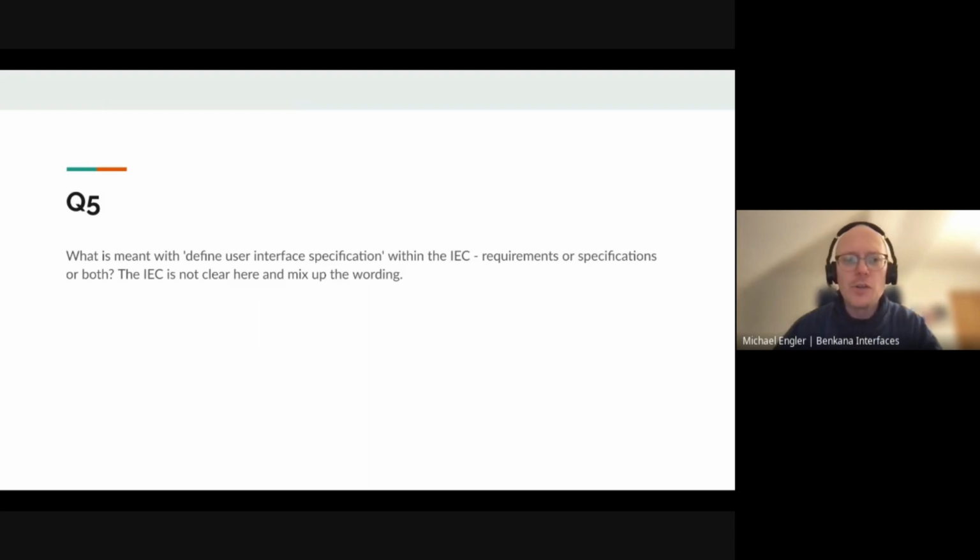So screenshots is not a good idea. What I do is wireframes because I then have a software requirements engineer or a software tester who actually looks at the wireframe, has a test case to actually ensure that the wireframe looks as it was in the specification, in the requirements. And this can be part of your software requirements according to 62304.